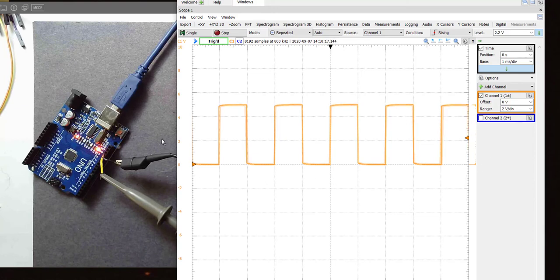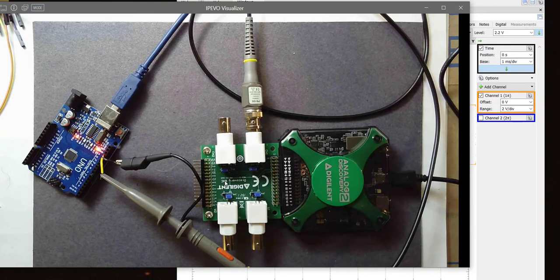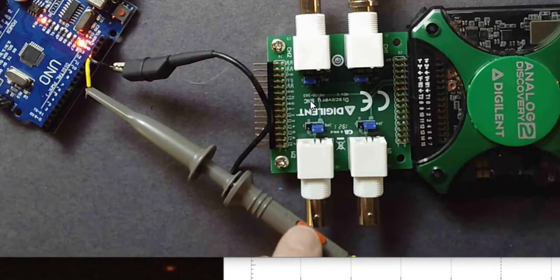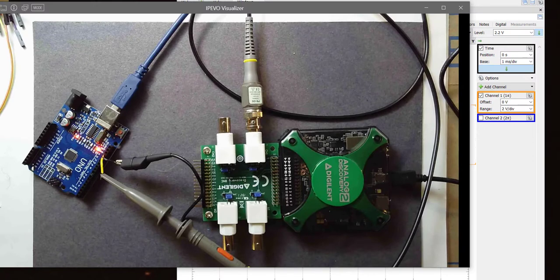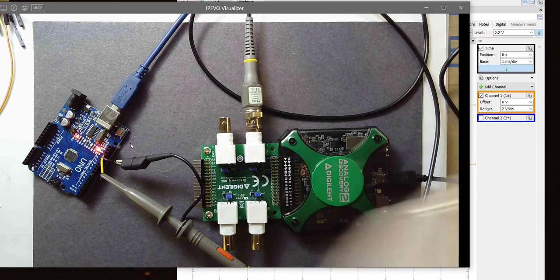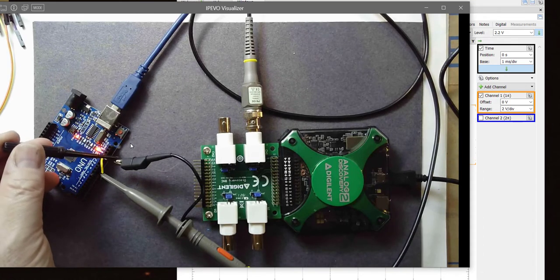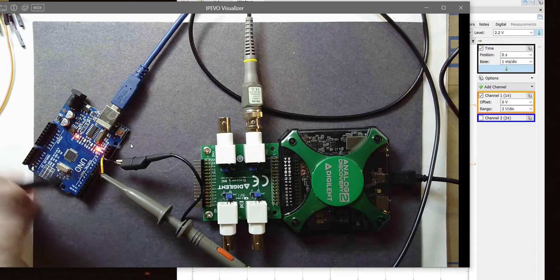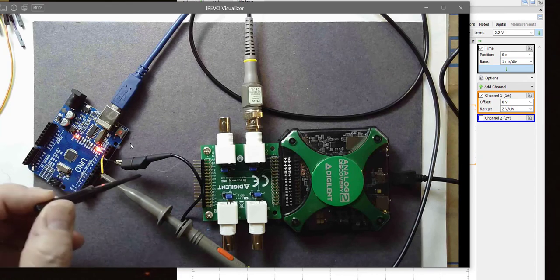So first, we set the DC connection on the hardware of the BNC adapter. Second, we adjust the 10x attenuation setting in the scale. Third thing that we want to do is just make sure that the adjustment over here on the 10x probe is set for 10x and not 1x. And we'll see a little later where the 1x comes in. And then the fourth important thing is to make sure that when we make the connection to the device under test, we're using as short a connection as practical between the signal of the tip and the return of the tip. We have this long loop here already. We just don't want to make it any longer.